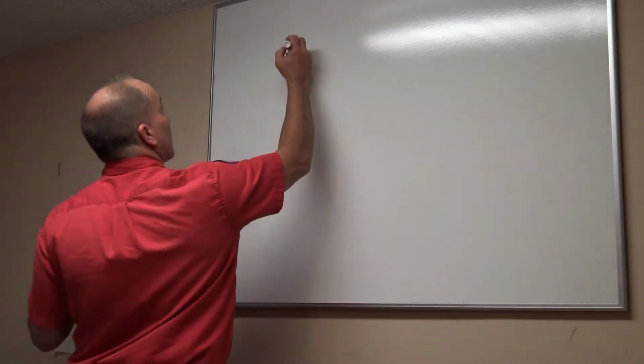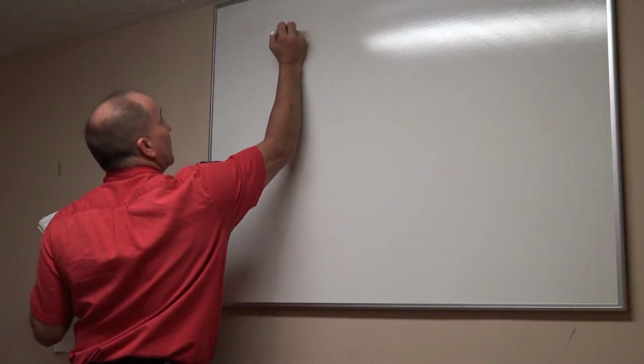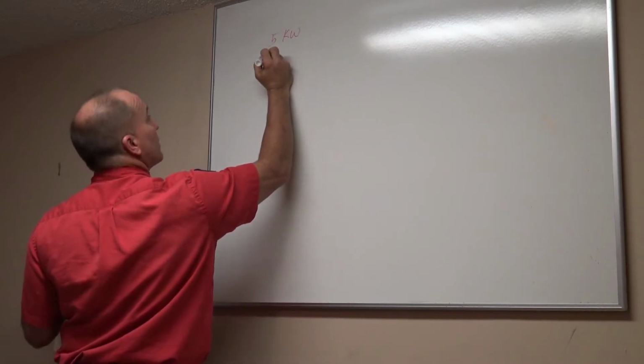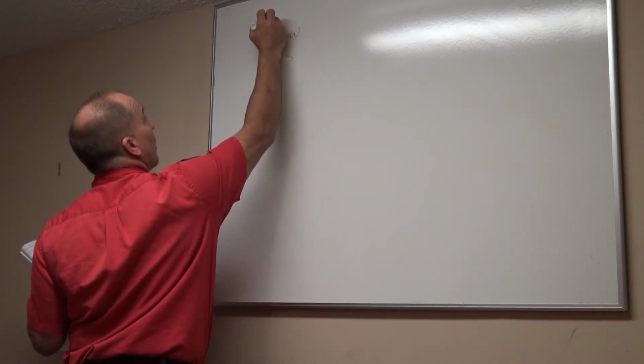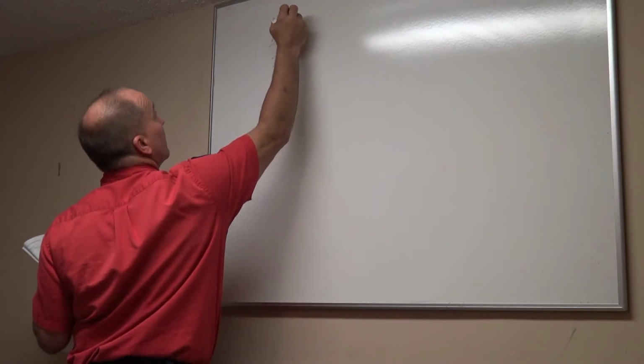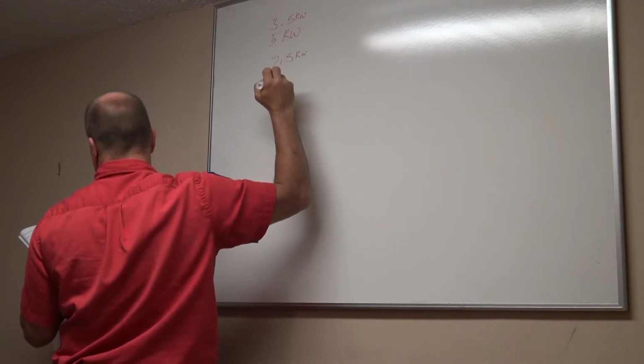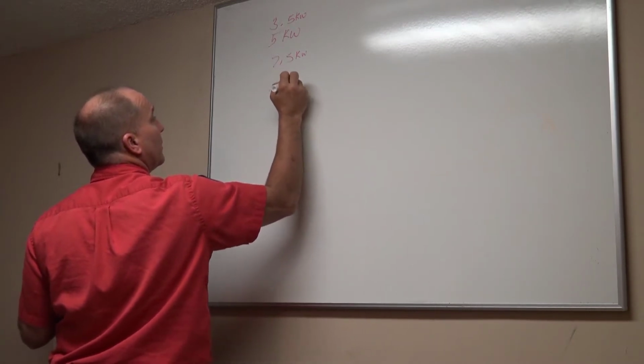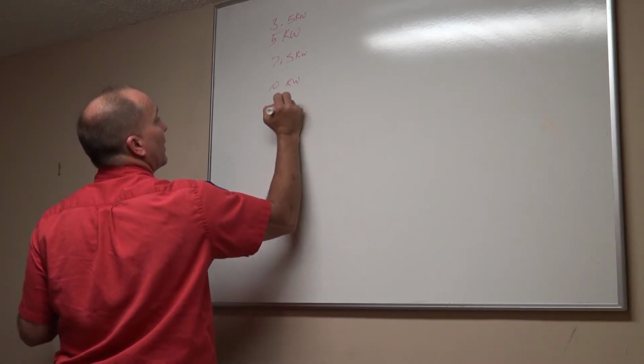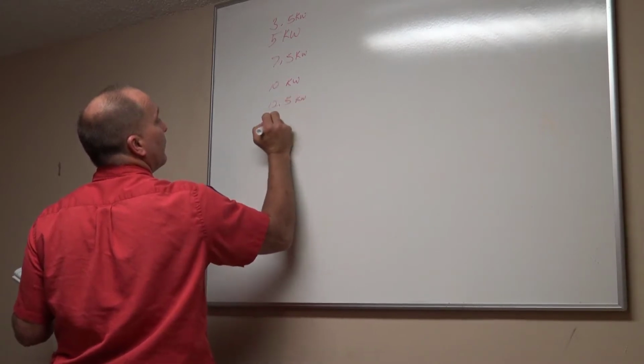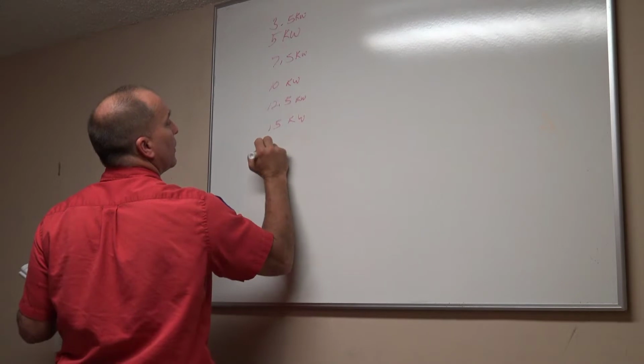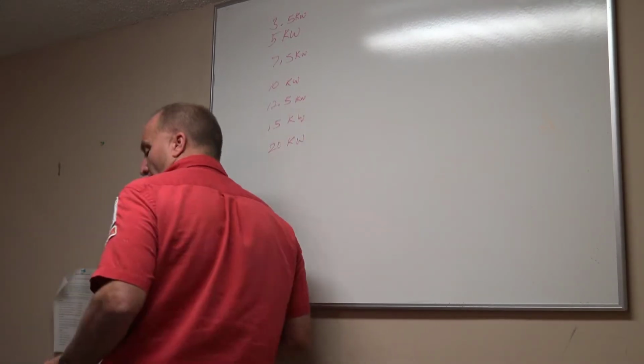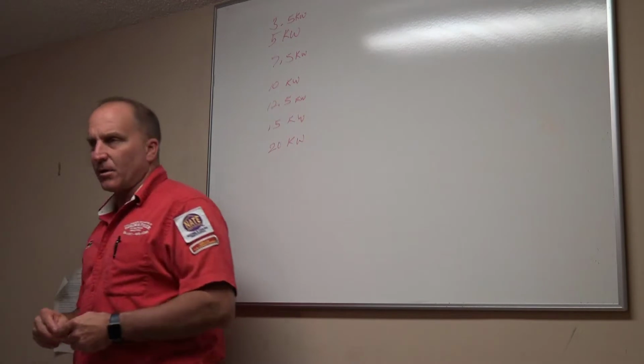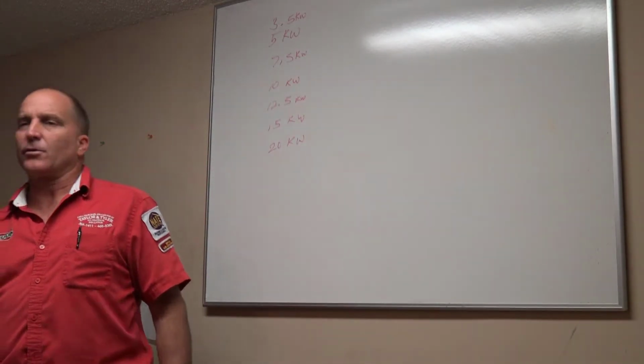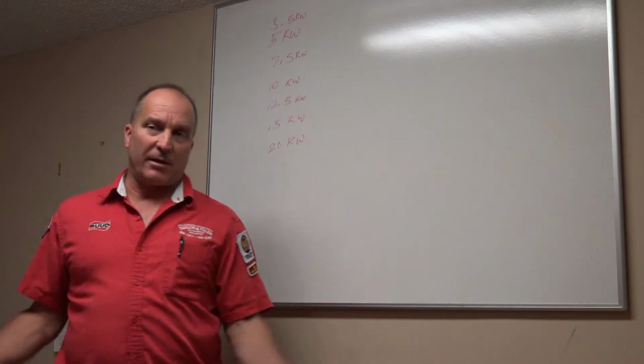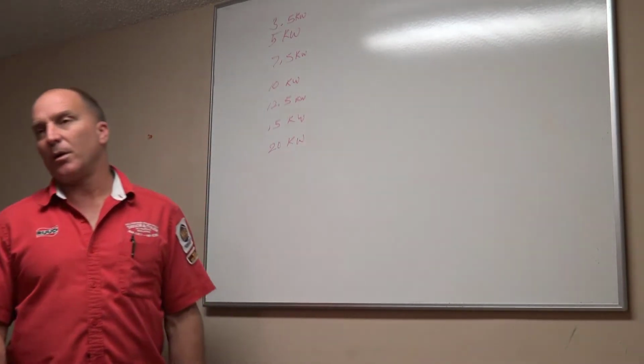So we're going to start off with 5 kW, and we're going 7.5. Actually, we'll start off with a 3.5 kW, 7.5, 10 kW, 12.5 kW, 15 kW, 20 kW. That is about as high as we're going to go with residential air conditioning and heating with electric heat strips, is about 20 kW. I've never been in a home that had more than 20 kW, because then you're going into commercial with 7.5 ton systems, okay?